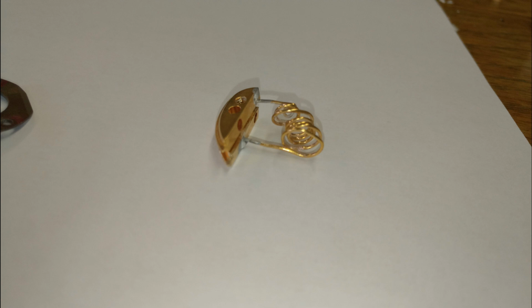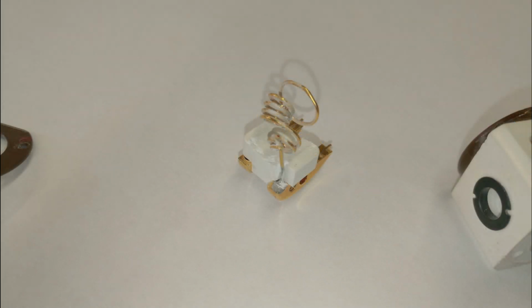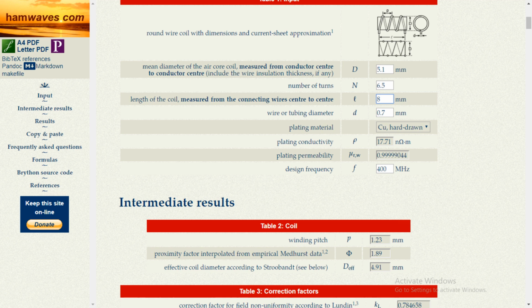The exploding rotor tangled the radio frequency solenoid coil. To make a new one, a lot of questions emerged. First, how the original looked like. Second, what wire was used in the original coil. Then, of course, I had to figure out how to make the new coil and how to solder it exactly in the rotor spinning axis.